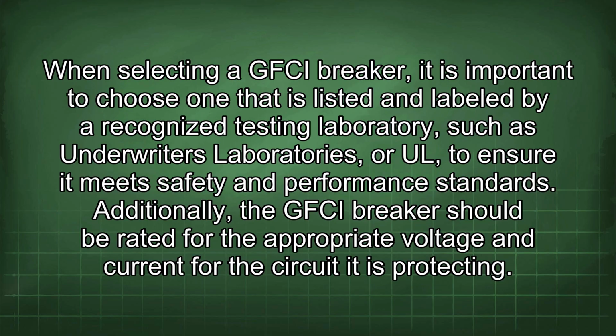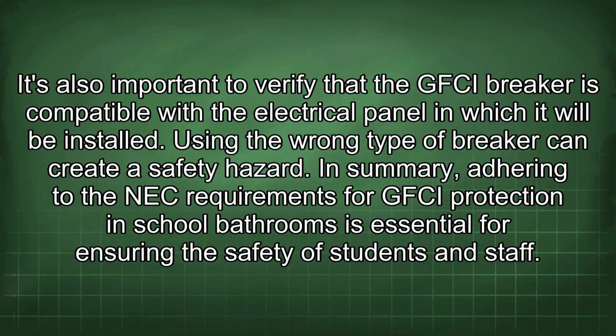When selecting a GFCI breaker, it is important to choose one that is listed and labeled by a recognized testing laboratory such as Underwriters Laboratories or UL to ensure it meets safety and performance standards. Additionally, the GFCI breaker should be rated for the appropriate voltage and current for the circuit it is protecting. It's also important to verify that the GFCI breaker is compatible with the electrical panel in which it will be installed. Using the wrong type of breaker can create a safety hazard. In summary, adhering to the NEC requirements for GFCI protection in school bathrooms is essential for ensuring the safety of students and staff.